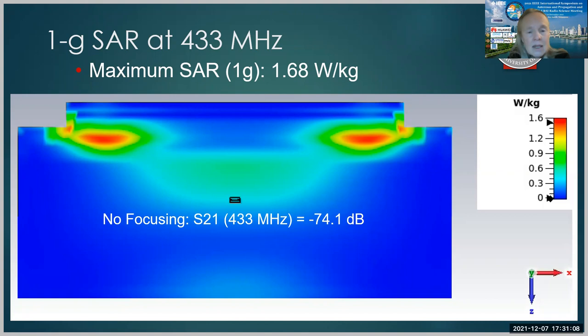Now, in the case where we have no focusing, the S21, the transmission between the external coil, which is port one, and the internal implant, which is port two, at 433 megahertz is minus 74 dB. Not very high, but considering that we have a large amount of lossy body, understandable.